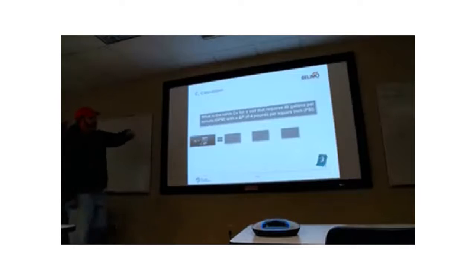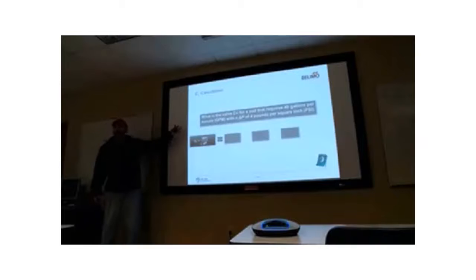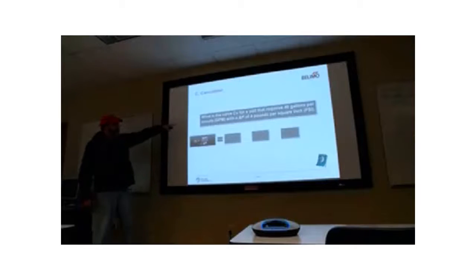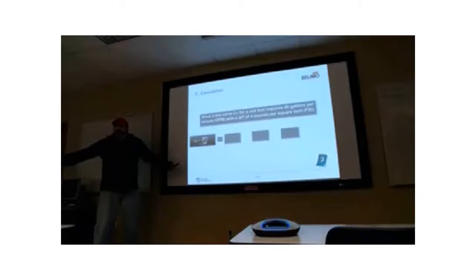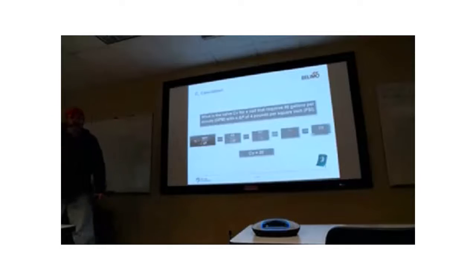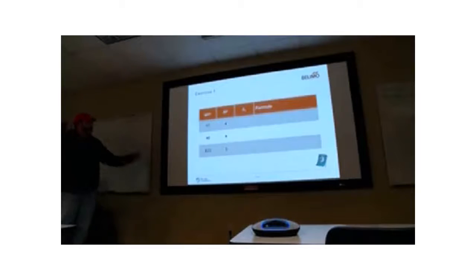So no, but really, that's the way these valves are picked. It's not this mystifying, voodoo stuff. A lot of valves get sized this way. Now, I'm not saying it's absolutely right, but it is done, and a lot of people do it. All right, so let's do it. We've got 40 GPM. We've got a pressure drop of 4 psi. What's the CV? 20. Easy. No problem. I'm not going to go through these.